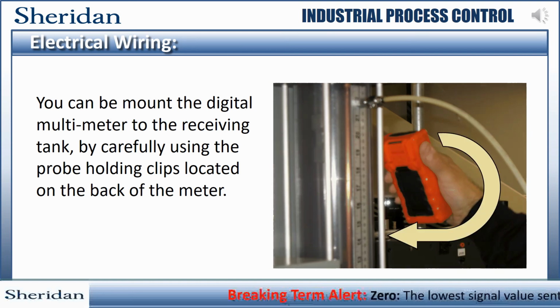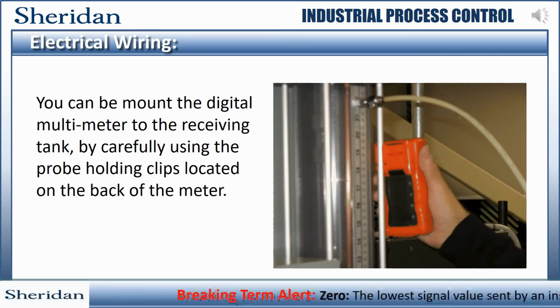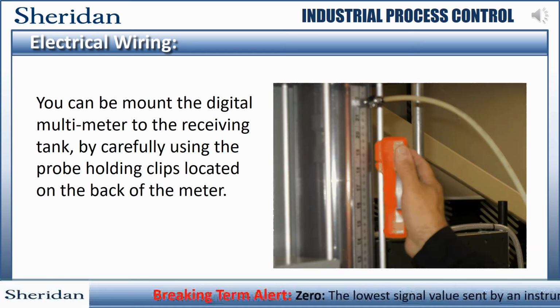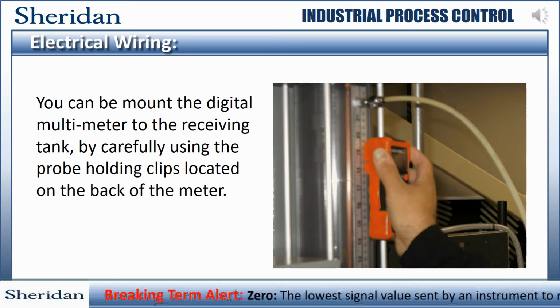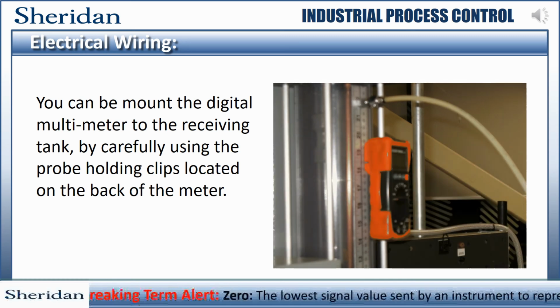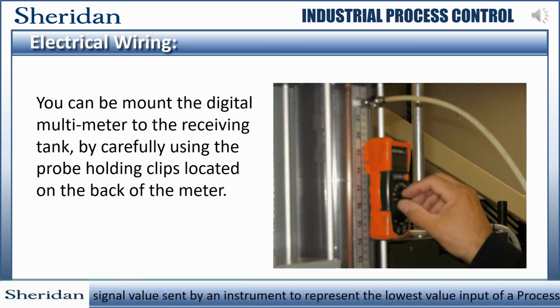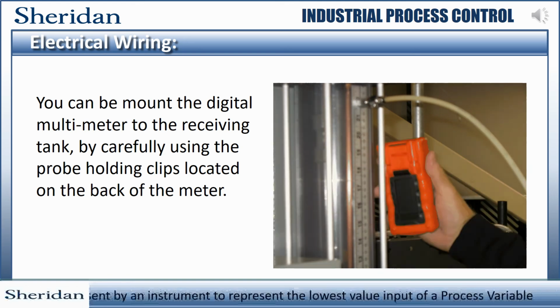You can mount the digital multimeter to the receiving tank by carefully using the probe holding clips located on the back of the meter. Simply take the meter and align one of the probe holding clips with the aluminum tie rod on the receiver tank. Starting from the top of the holding clip, apply firm but not forceful pressure to insert the tie rod into the holding clip, and then rotate the meter downward until the meter is fully secured. This will allow you then to slide the meter up or down for easy viewing.